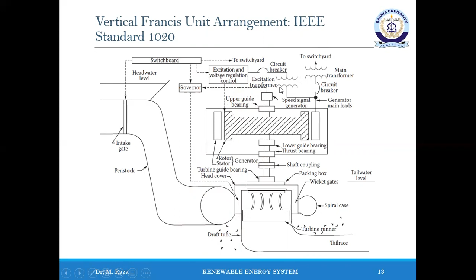The type of turbine selected for a particular application is influenced by the head and flow rate. There are two classifications of hydraulic turbines, that is impulse and reaction. The flow through the turbine is controlled by the wicket gates on a reaction turbine, such as shown over here, and by the needle nozzle on an impulse turbine. A turbine inlet valve or penstock intake gate is provided for isolation of the turbine during shutdown and maintenance. This is shown over here.